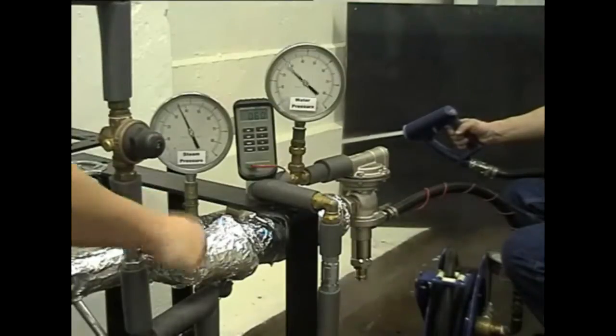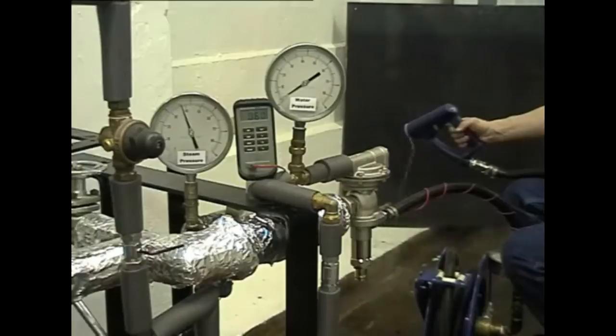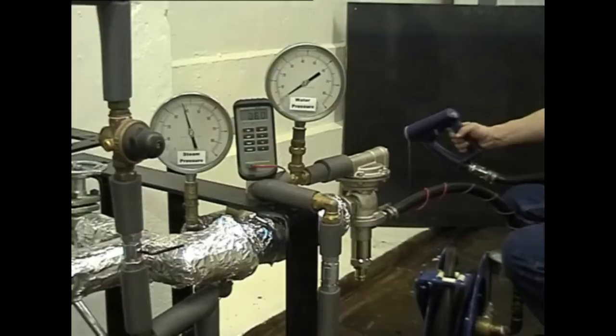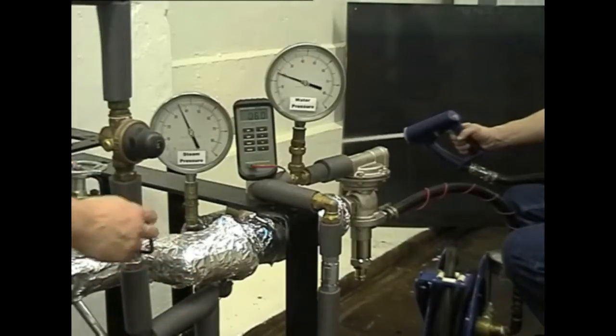The SWM1 does not pass live steam when there is no water flow through the valve. Closing the cold water supply instantly and completely stops any flow from the SWM1.